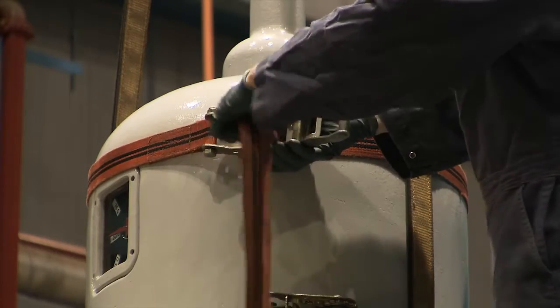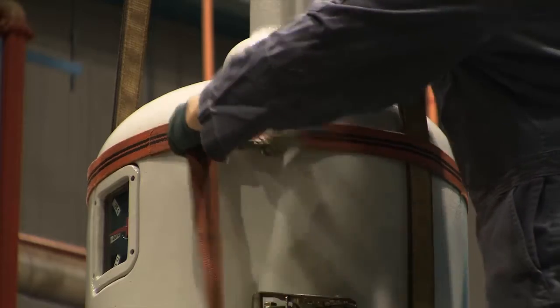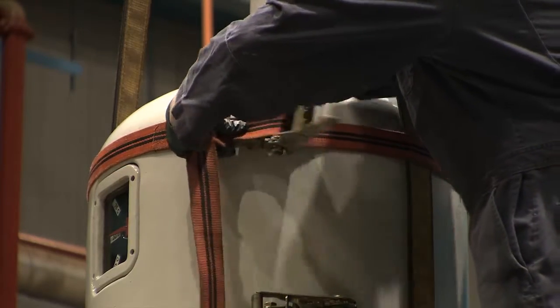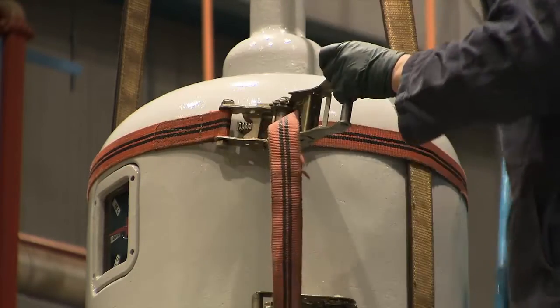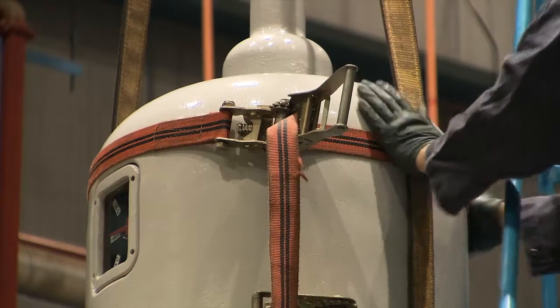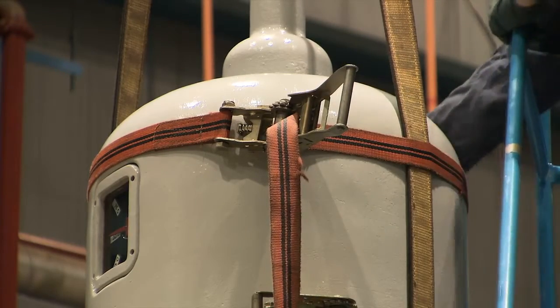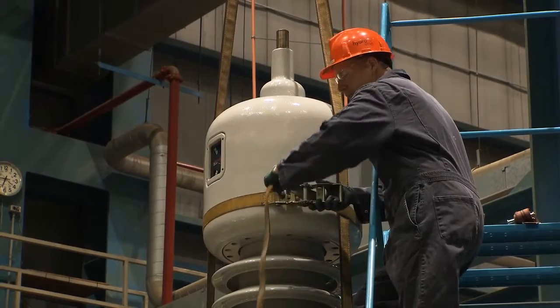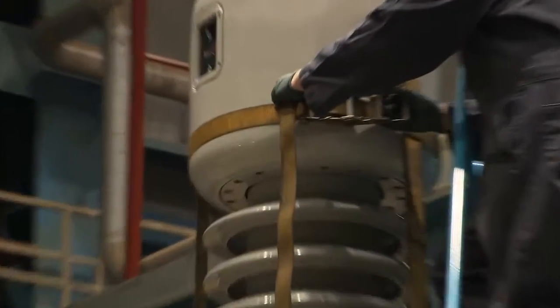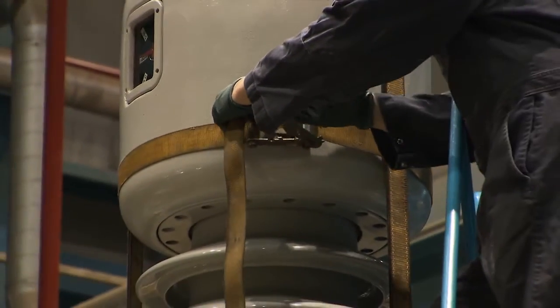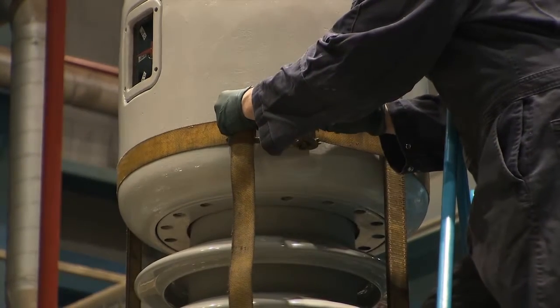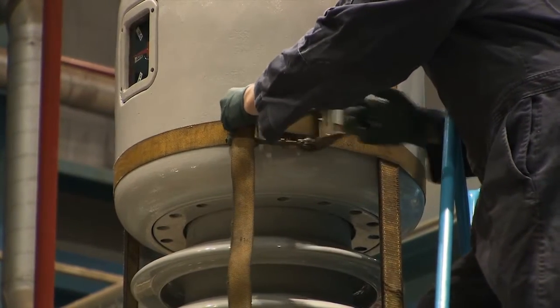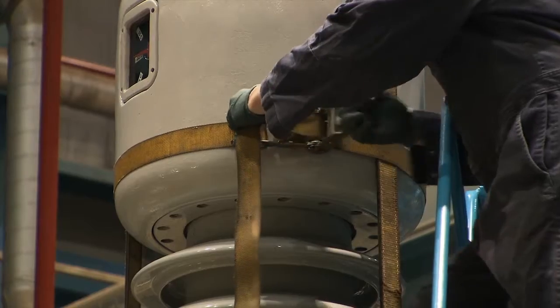Wrap the first tightening sling around the lifting slings on the upper half of the oil reservoir. The sling is wrapped around the oil reservoir through a buckle and tightened as much as possible. Wrap the second tightening sling around the lifting slings on the bottom half of the oil reservoir. The sling is wrapped around the oil reservoir through a buckle and tightened as much as possible.